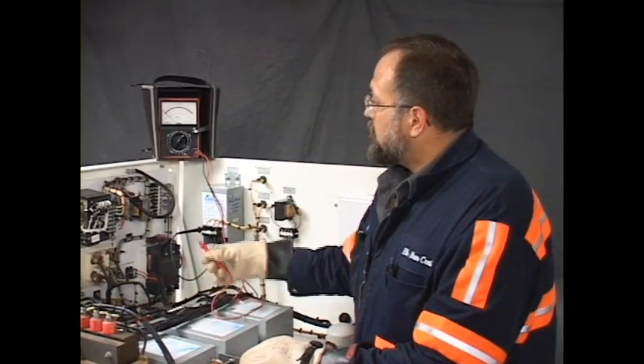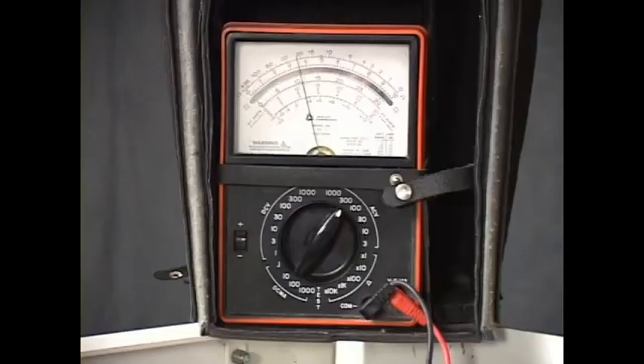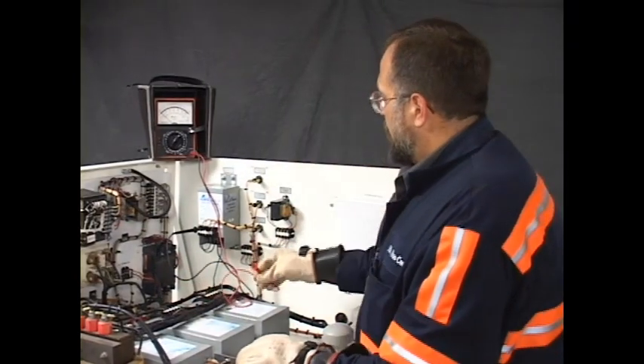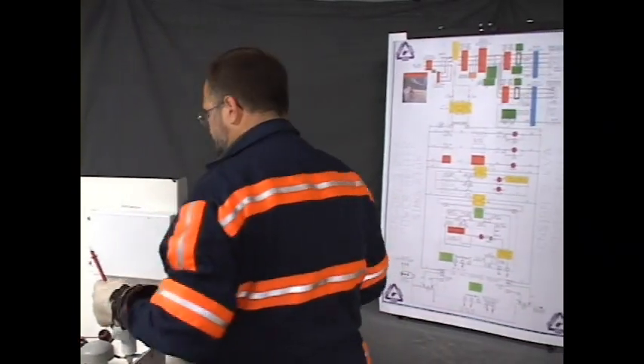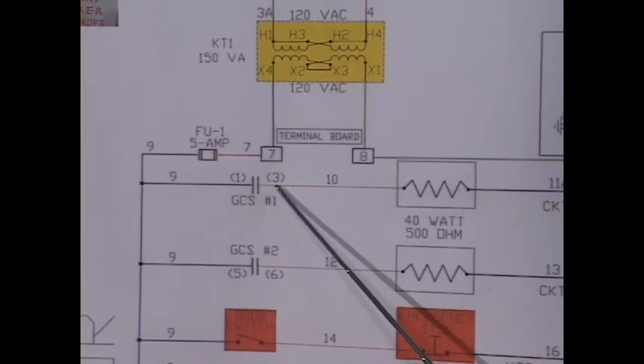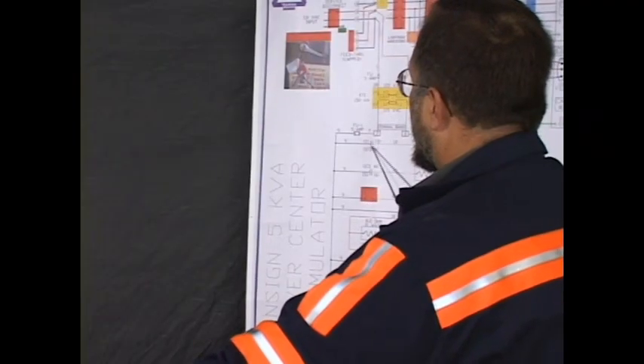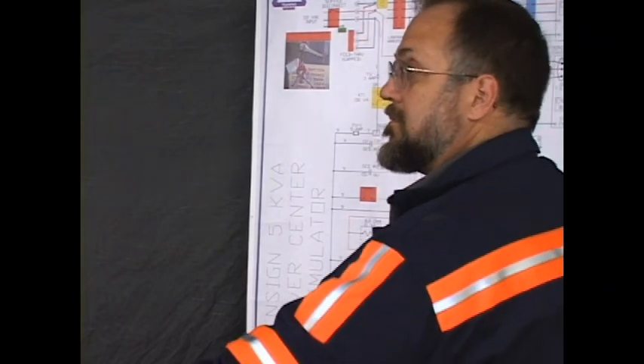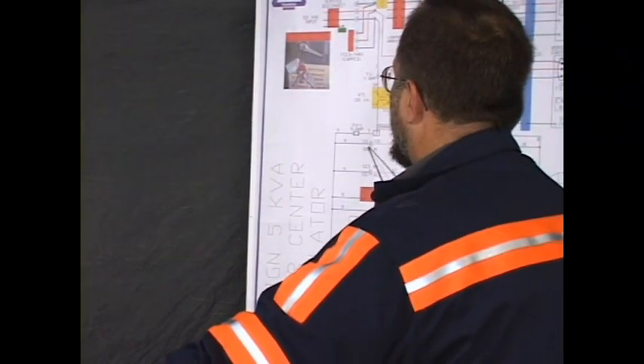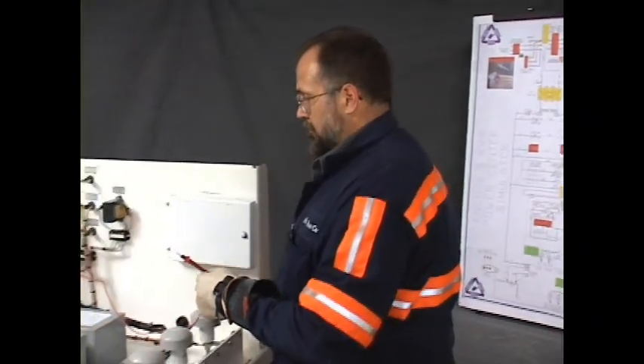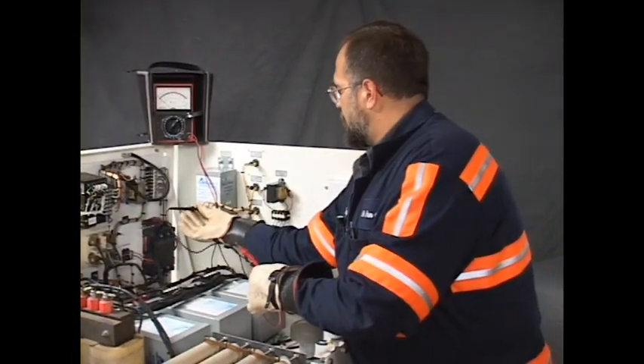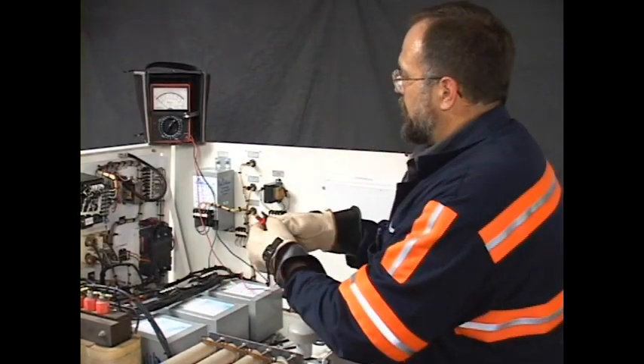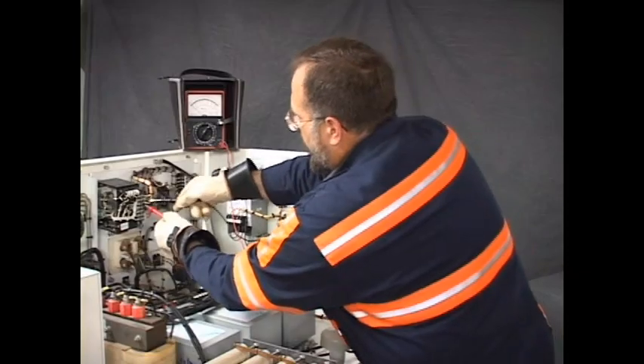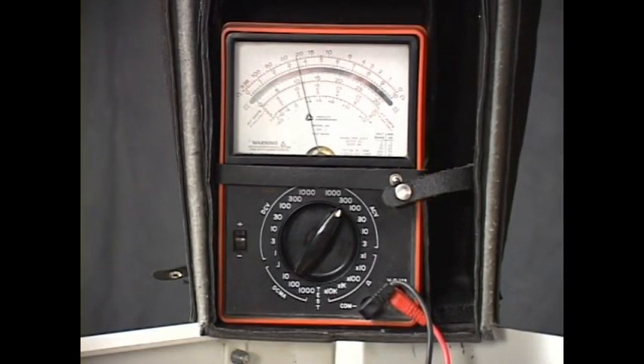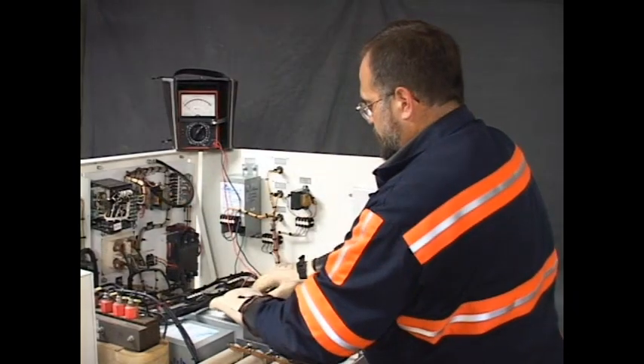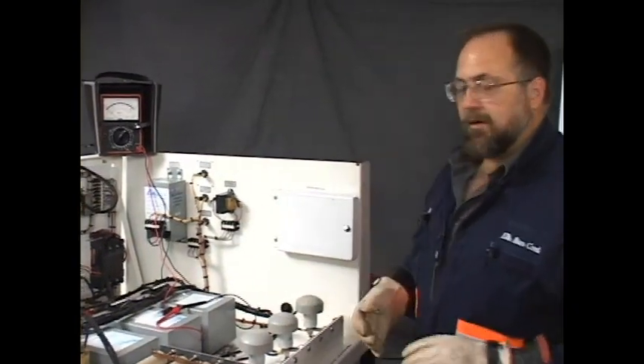The next point I will read is terminal 10. There we have it. Wire number 10 on terminal 3, I read 120 volts right here. If this contact were closed, then there would be no difference and it would read the same. But in fact, it's open. To further pinpoint that, I'll take a probe and read from 9 to 10. I read 120 volts.